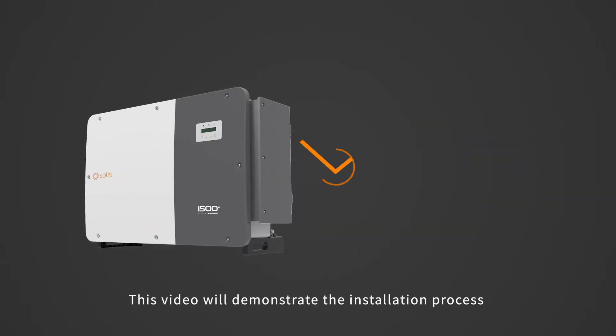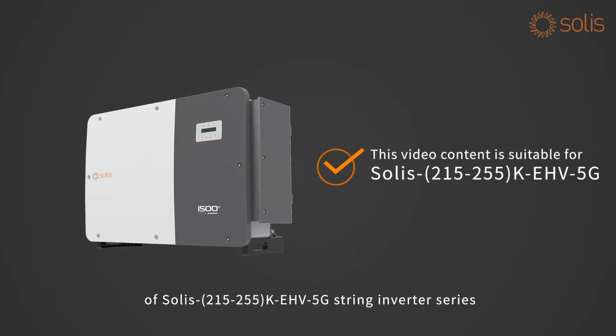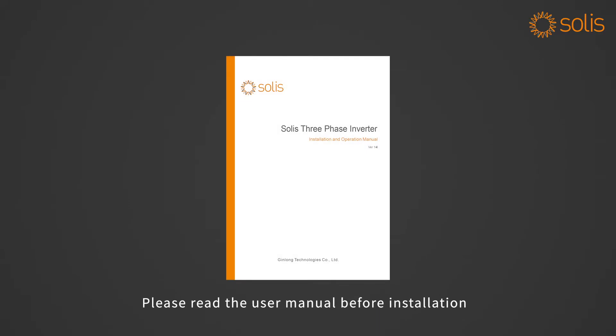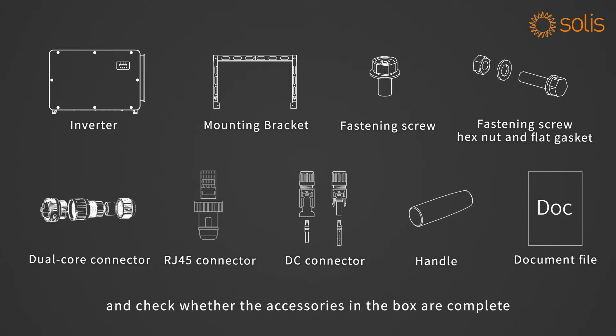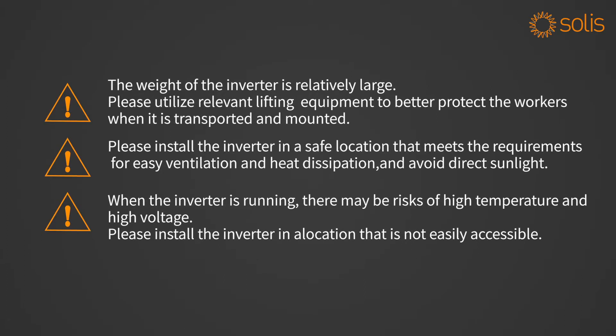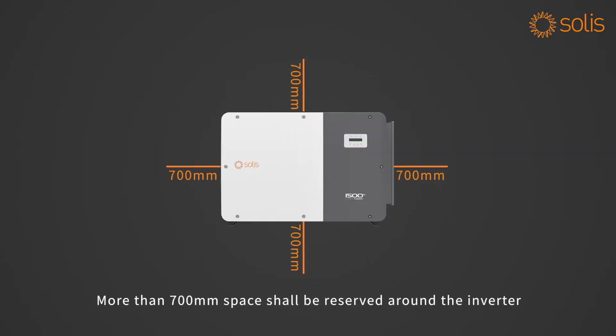This video will demonstrate the installation process of Solis 215 to 255K EHV 5G string inverter series. Attention: electrical equipment can only be installed and maintained by qualified electrical technicians. Please read the user manual before installation and check whether the accessories in the box are complete. More than 700mm space shall be reserved around the inverter.